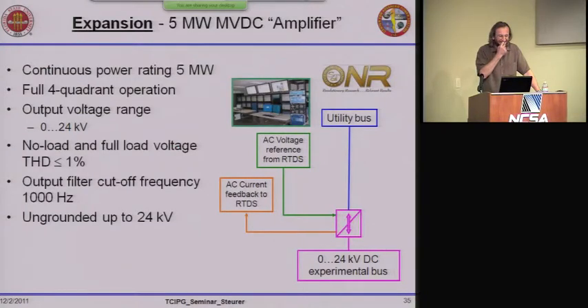We're also expanding into another regime: medium voltage DC, particularly spearheaded by the Navy. In power electronic-based distribution systems, every device connected to the distribution line has a power electronic interface, with no direct connection of a classical transformer or rotating machine. So the reason for 60 Hertz AC goes away. Most of these power electronic devices have a DC bus anyway, so why not move out these inverters and go to DC? This makes a lot of sense for ship systems, with a rectifier right at the 4, 5, or 6 generators, dealing just with medium voltage DC.